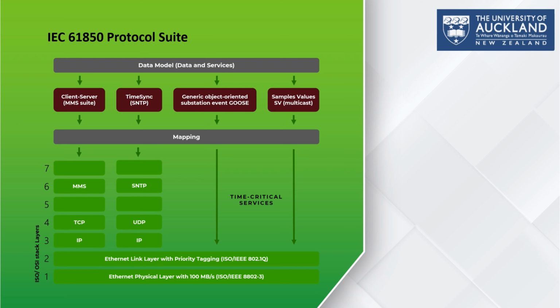So this includes four key service types, which are client-server, that is MMS, Manufacturing Message Specification, for monitoring, control, and reporting; time sync, we call it SNTP, for synchronizing all devices in the substation; GOOSE, which supports rapid peer-to-peer messaging for protection and interlocking functions; and sampled values, in short we call it SV, which deliver digitized measurements such as voltage and current from merging units.